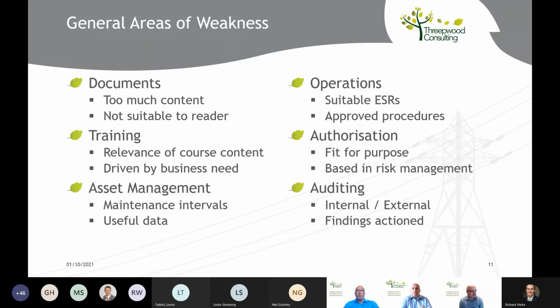Asset management wise, maintenance intervals can vary greatly between companies, normally based upon risk profile and asset knowledge. As-found data is tremendously useful to establish the general condition of your plant and network, but it's frequently overlooked. Trip testing circuit breakers is an excellent idea to ensure they work when called upon. A programmed periodic test of each circuit breaker is probably one of the most effective maintenance strategies to implement, because it gives you confidence in the safe operation of your plant.